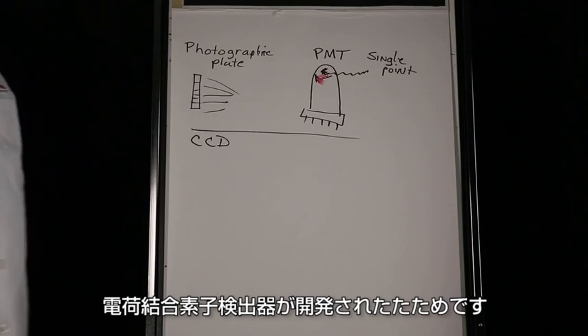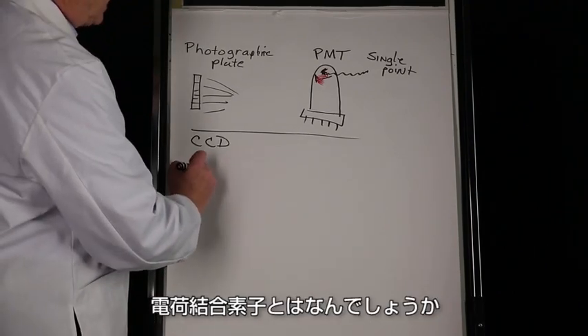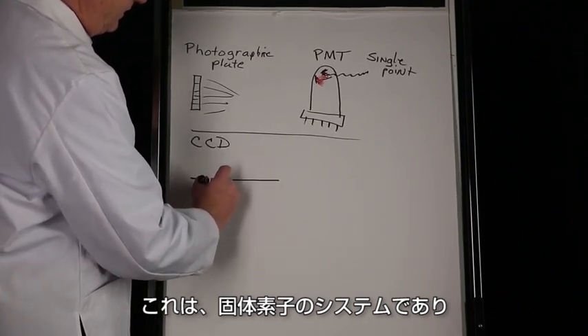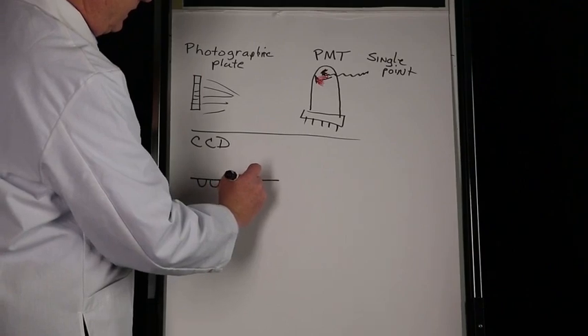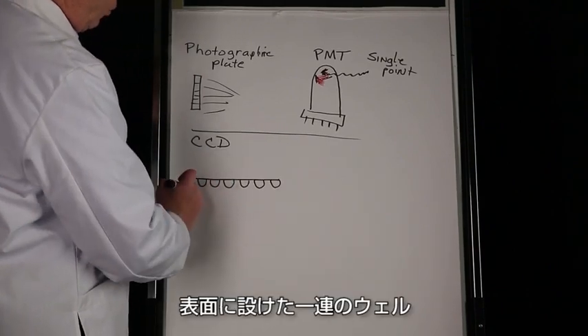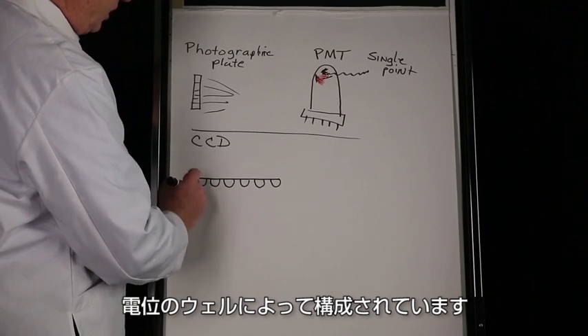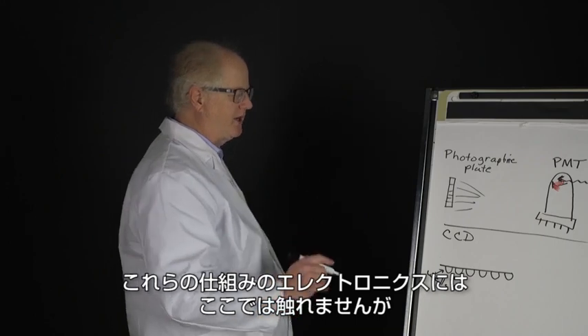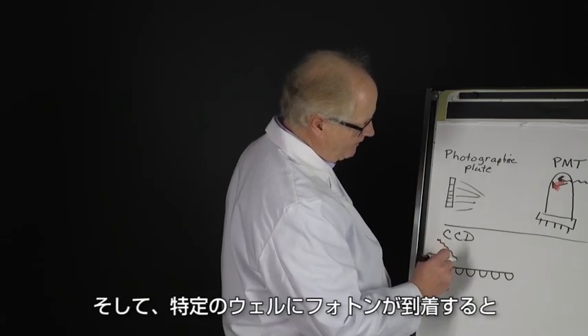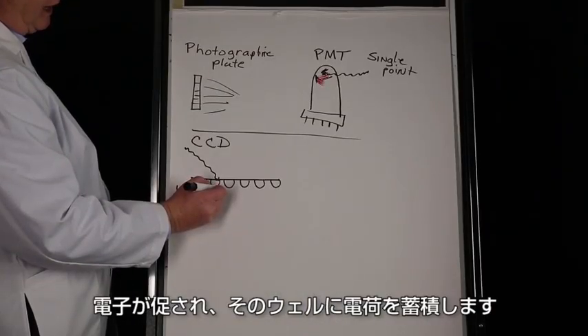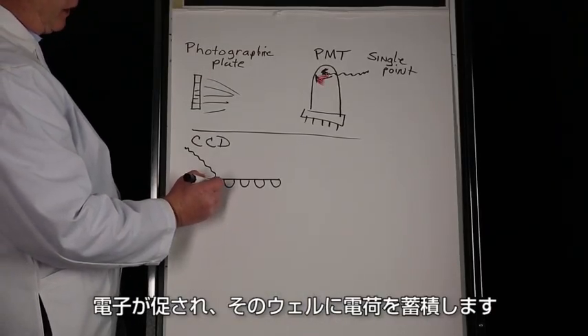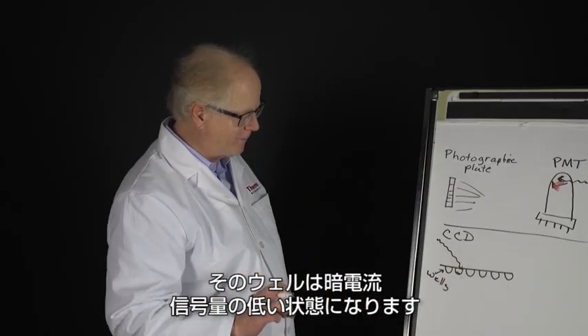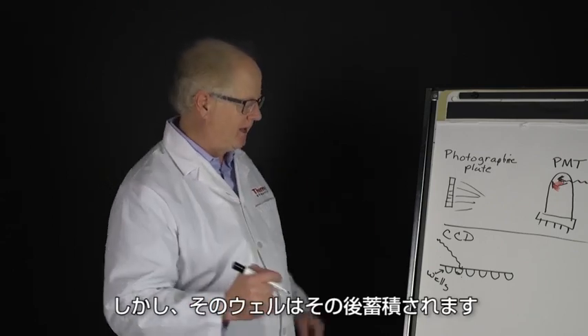All of that really changed and surged to the forefront with charge-coupled device detectors coming online. What a charge-coupled device detector is, is a solid state system consisting of a series of wells, electronic wells on the surface. We'll call them wells. And then when a photon arrives in a particular well, an electron would get promoted and we would begin to fill up that well. If no electrons arrived, the well would just have a dark current, a low amount of signal, but then the wells would build up.